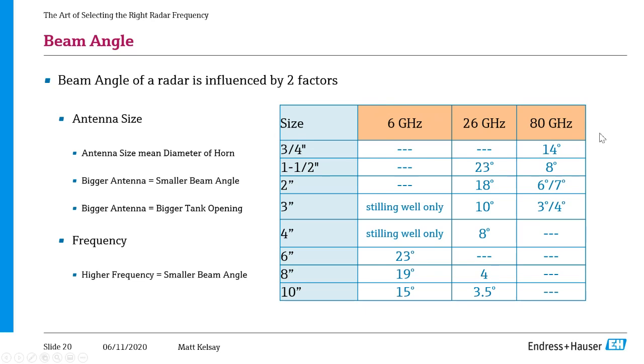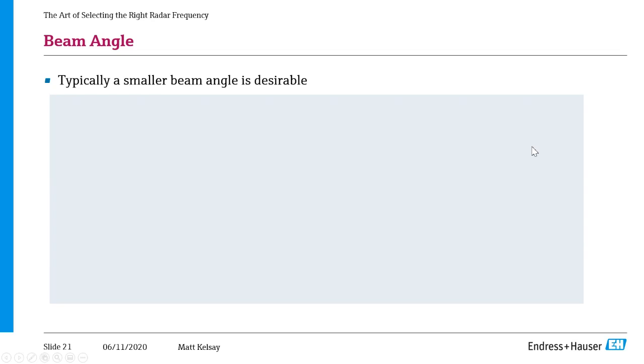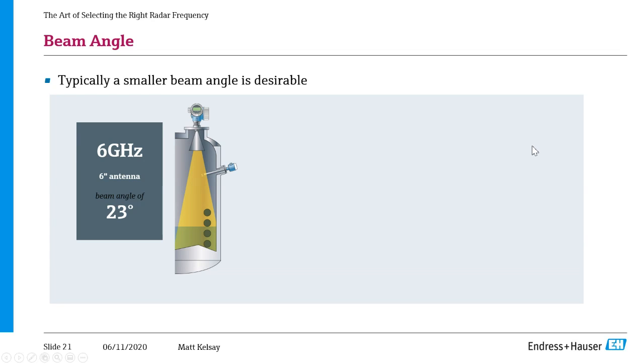Going to the next. So here we'll just show this pretty much the same thing, just in picture form. I like pictures personally to help me learn, so we'll put this up here for you guys. So the first shows a 6 gigahertz low frequency radar, a big 6-inch antenna. So you can see that antenna's got a big diameter. That means you've got a big opening in that tank, but still a big beam angle. You can see that signal in yellow there. It's probably going to hit the tuning fork or switch you've got put into the side of your tank. You're going to see those heating coils or baffle plates down in the bottom of the tank as well.